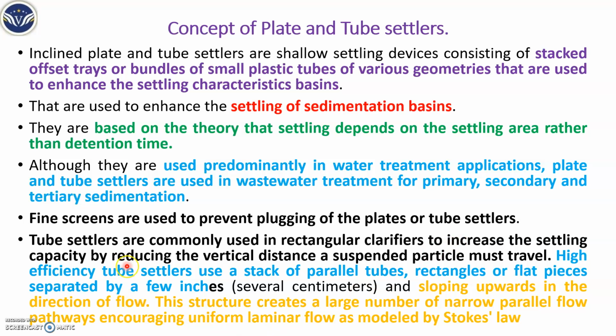Plate and tube settlers are common in rectangular clarifiers. They tend to increase settling capacity by reducing the vertical distance a suspended particle must travel.